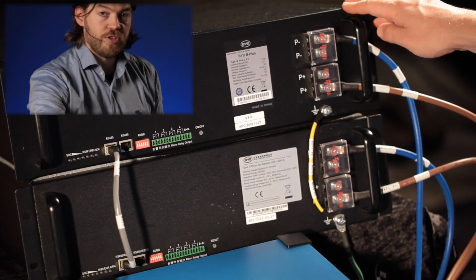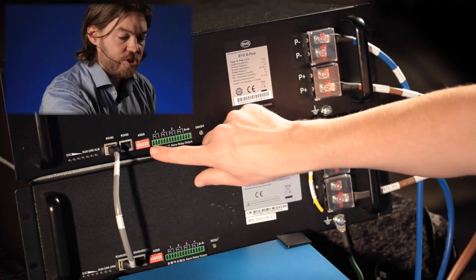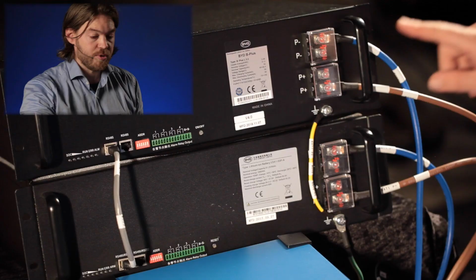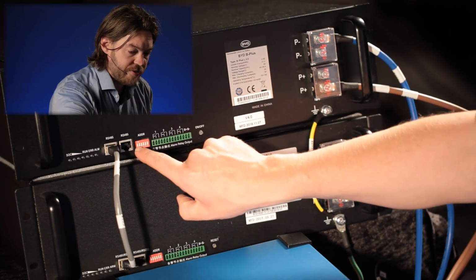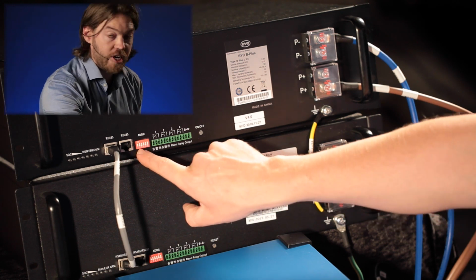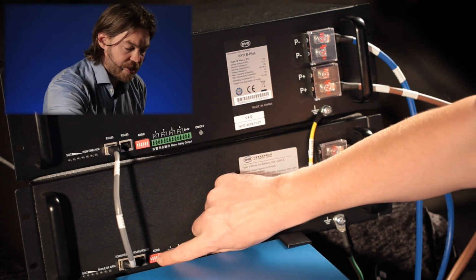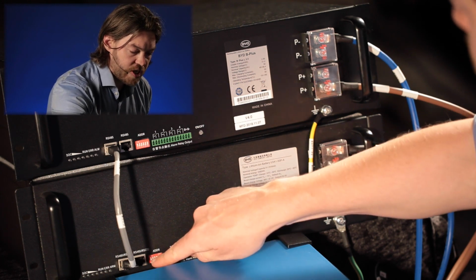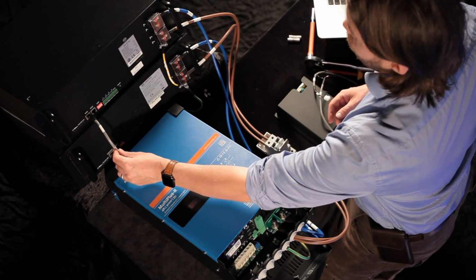While I'm here, I'm also going to do the addressing on the batteries. Now the specific addressing of the batteries should be referred to in the BYD manual. Effectively though, each battery needs a number in sequential order, starting by 1 and moving to 2 to 3 to 4 to 5 to 6 and so on. This is done in a binary code on these dip switches. So I'll make the first battery here number 1 by sliding the first dip switch up, and I'll make the second battery here number 2 by sliding the second dip switch up. If you have more battery modules, you'll have to refer to the manual on how to program those with that addressing system and connect them with the RS485 cable. But for 2 modules, that's how this is done.